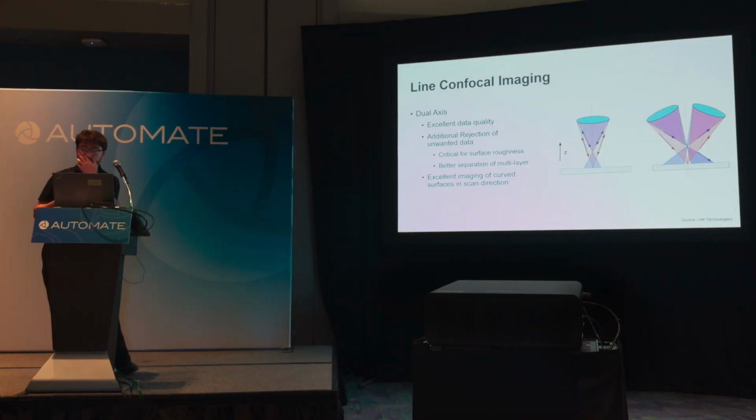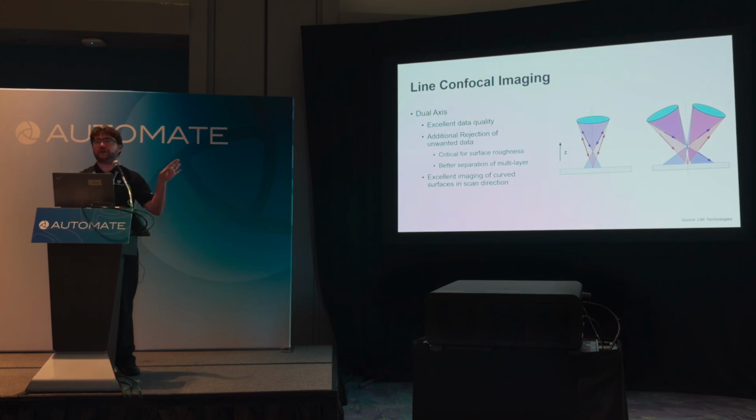Dual axis, the main advantage you get there is even more noise rejection. This sensor configuration is also a lot more sensitive. Not only because of the reflection path, but because in a coaxial sensor arrangement, you have to put the light through a beam splitter, and you have to put it through twice. So the light that's going down onto the sensor passes through a beam splitter, and then when it comes back up, it also goes through another beam splitter, so that's a factor of 4 times difference in sensitivity between a coaxial arrangement and a dual axis.